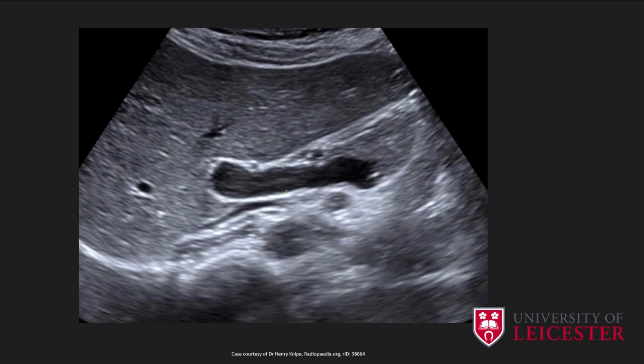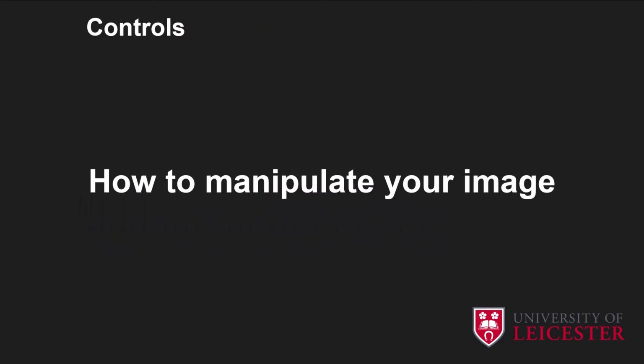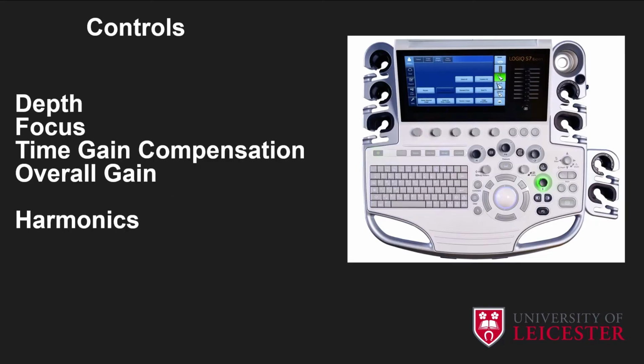with the controls. Unlike some other imaging modalities, ultrasound is extremely user dependent, as we've said. The quality of the images obtained will depend a great deal on the technique used to obtain them. An important part of image optimization is developing a familiarity with the control panel of the ultrasound machine. So that's what we'll look at next. To be able to drive the machine and manipulate the image as you want it, you need to know about depth, focus, time gain compensation, and overall gain. And we'll also look at harmonics.